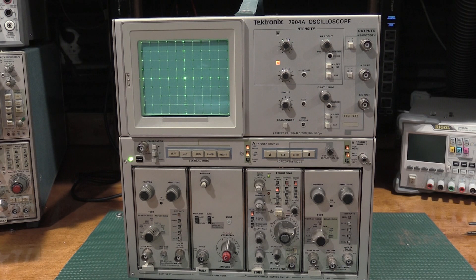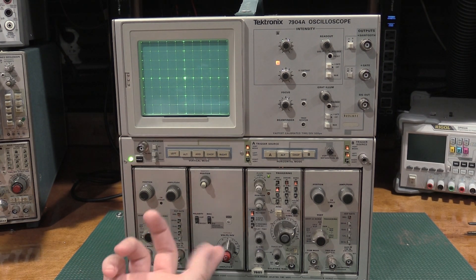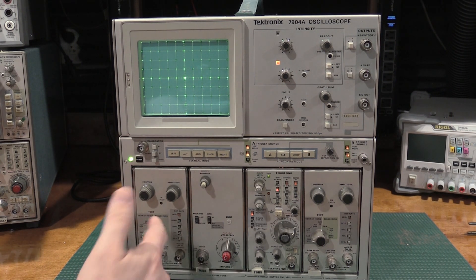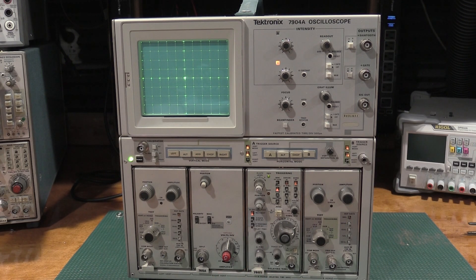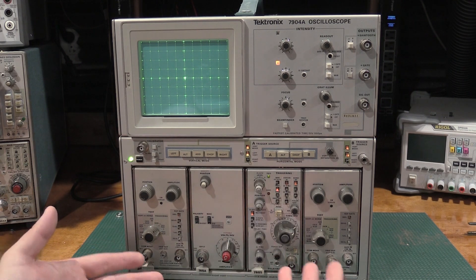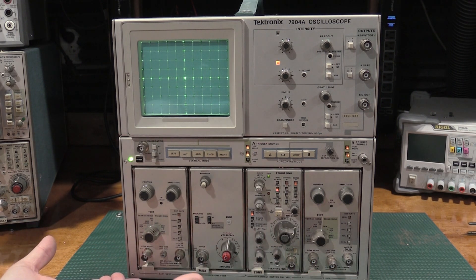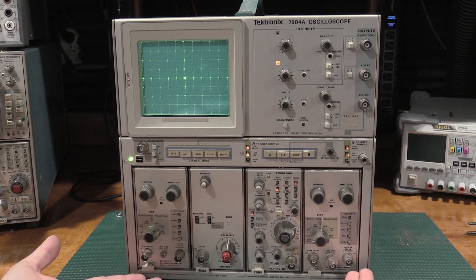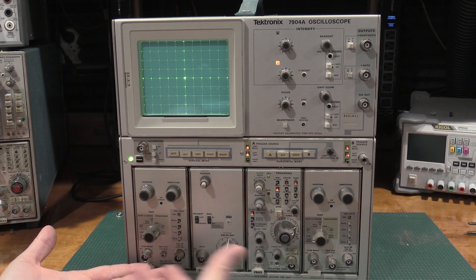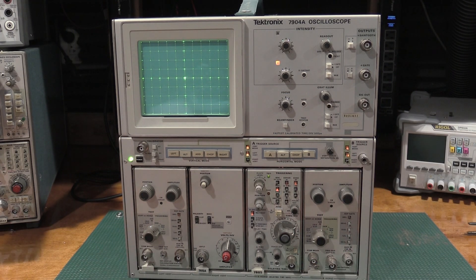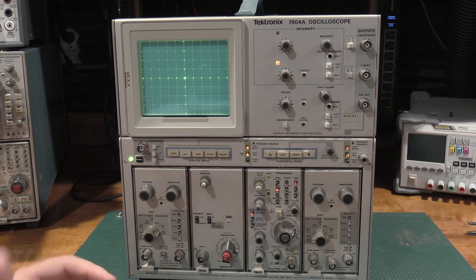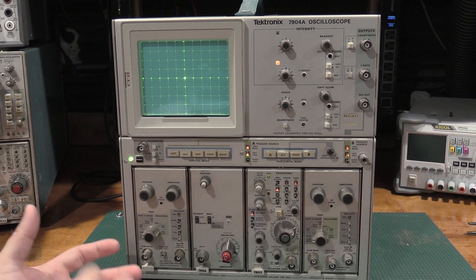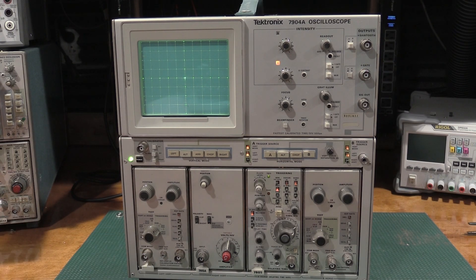It's the same gain and response circuits for triggering and all that other thing, and all the other stuff. It's just a matter of what's doing the readout on the display, so you're balancing, essentially you're standardizing the response across all of the plug, all of the ports in the front of the frame, so as you move plug-ins around, move plug-ins to other scopes, everything stays within spec.